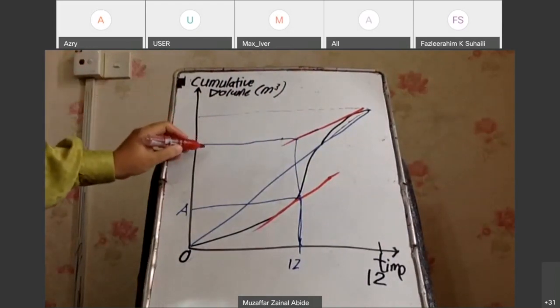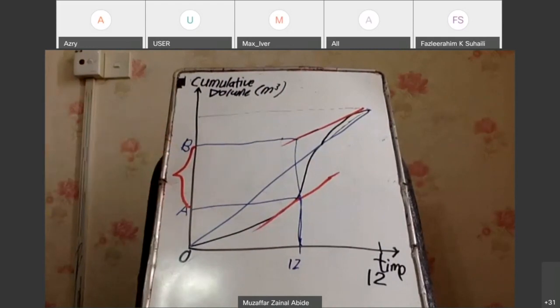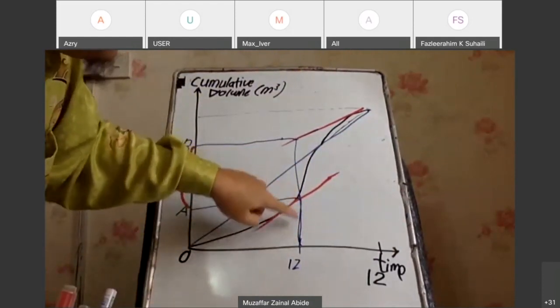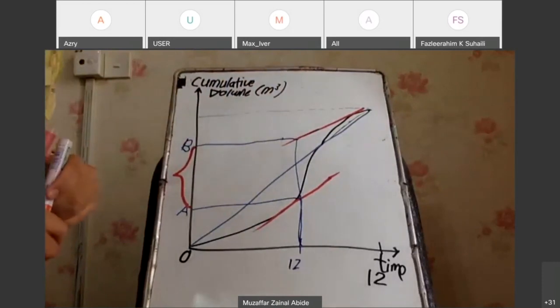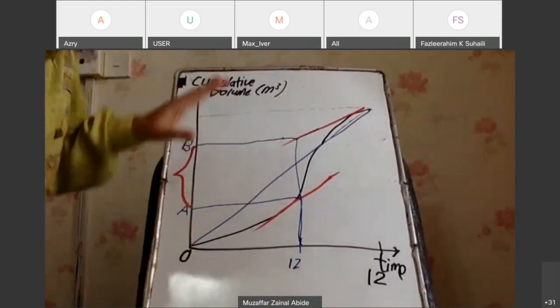The volume for equalizing demand is B minus A. To summarize: when the pump is on for 24 hours, draw two tangents — one at the minimum and one at the maximum — then pick any time, say 12 o'clock. Read the volume at the first tangent as A and the interception at the second tangent as B. The equalizing demand volume equals B minus A.